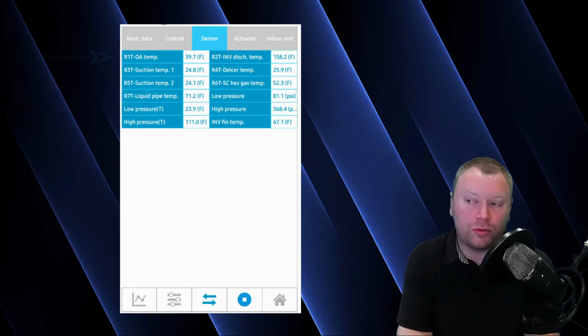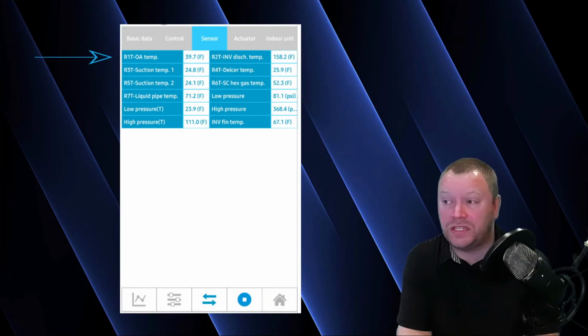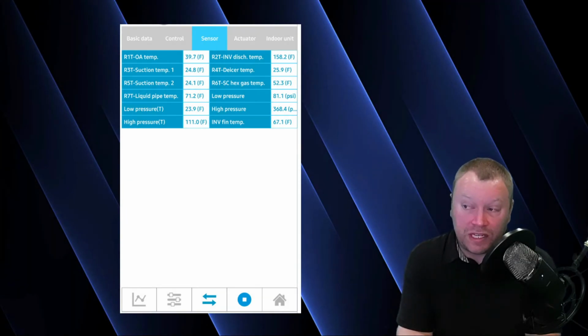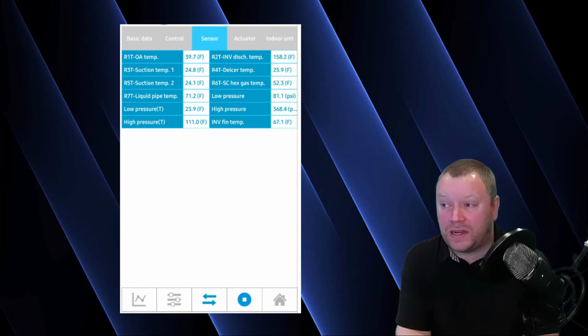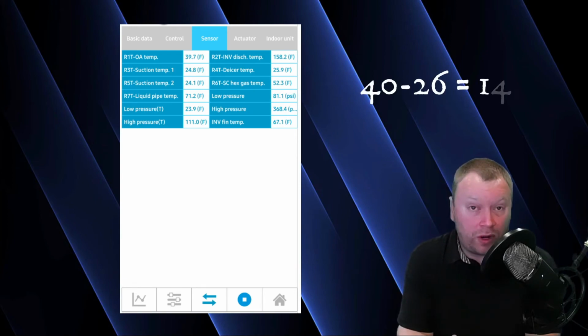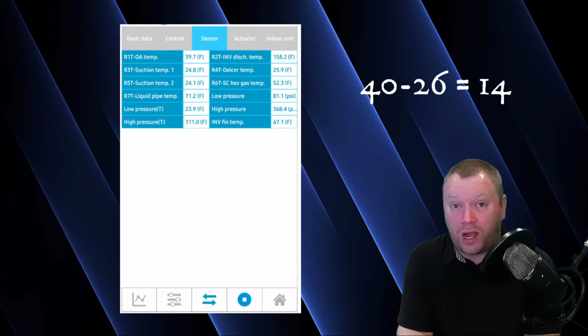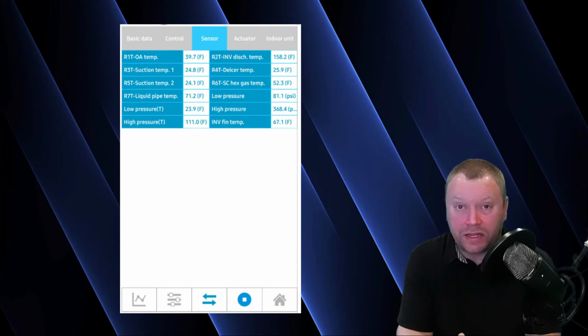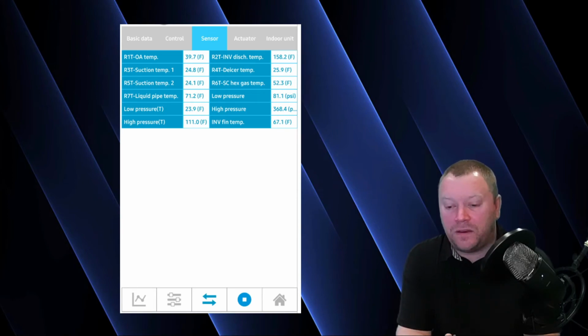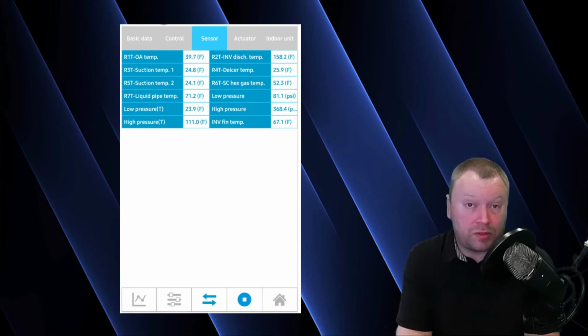If you see the outdoor temperature at 39.7 degrees here, and you look at your de-icer temperature at 25.9, we're right around a 14 degree drop from ambient down to that de-icer temperature. So we're right at the maximum range of how far we would want it to be. If it was dropping too far, then that outdoor expansion valve could start to open up. The outdoor expansion valve is also going to be controlling volume of refrigerant.